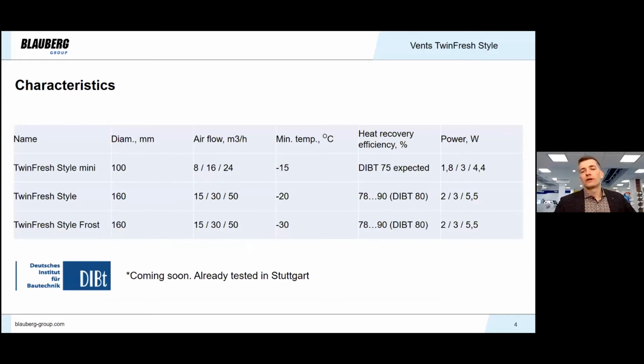Let's take a closer look at the three basic units. First one is TwinFresh Style Mini with a 100 mm duct. The maximum airflow is 24 cubic meters per hour in ventilation mode. As you understand, in heat recovery mode this should be divided by half. Minimum operation temperature for this small unit is down to -15. Next month, a sample of this unit will be sent to Stuttgart for precise testing in an independent third-party laboratory. So we expect the TwinFresh Style Mini to show about 75% heat recovery efficiency. And we will discuss with our customers whether we need a DIBt certificate after that. We will see.